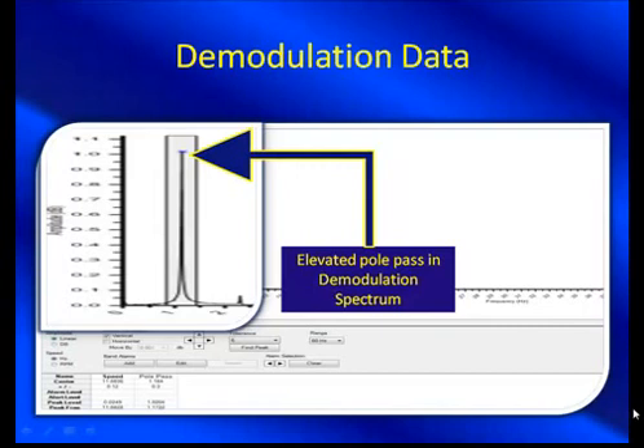What about offline? What would we look for offline if we wanted another way of looking at a potential problem with this motor? Filling in the six tests we talked about up front — the rotor influence check is a great tool for offline indications of rotor defects and eccentricity. Trending of the inductance value is another very popular tool. All of those are pointing towards rotor. So we're going to pull this rotor, and after the 14 to 19 weeks, let's see what this rotor actually looks like.